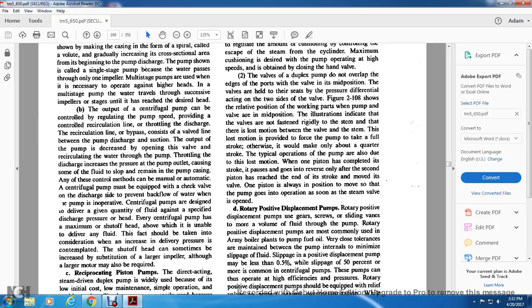The output of a centrifugal pump can be controlled by regulating the pump, provided with a control recirculation line, or by throttling the discharge. The recycling line, or bypass, consists of a valve and line between the pump discharge and the suction. The output decreases with the opening of the valve. Throttling the discharge increases the pressure at the pump outlet, causing some of the fluid to stop and remain in the pump casing.